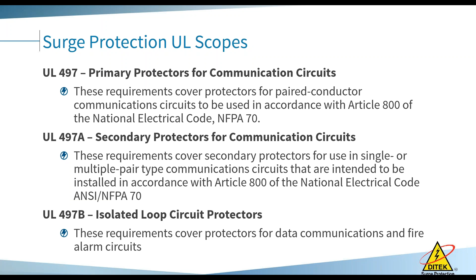Talk about SPD location requirements. Obviously, you've got one at the main service coming in. Utility fed power obviously is the main spot where surge can come in to a property. You never know what's coming from that pole. Most of these things are above ground, or if it's a nicer neighborhood, they're buried below ground, which is even more chance for them to bring surge into your building or house. You could also put it right at the circuit panel, receptacle outlets more than 10 meters away. There's also type 3 over there.